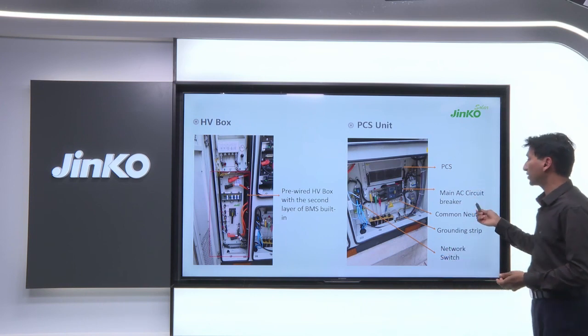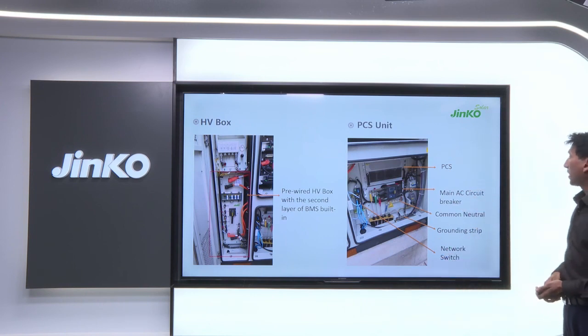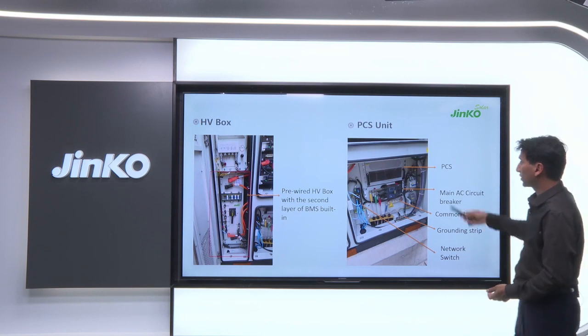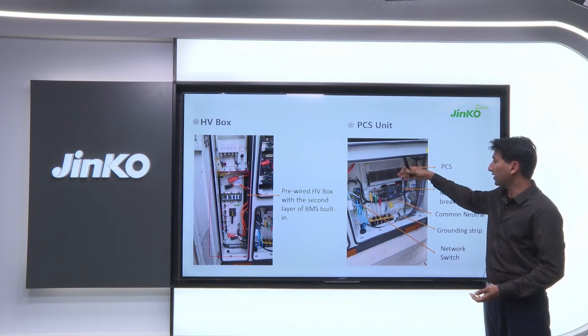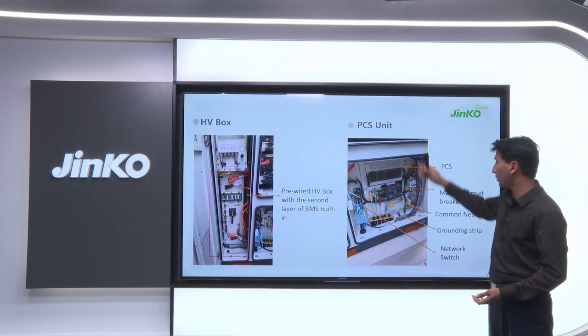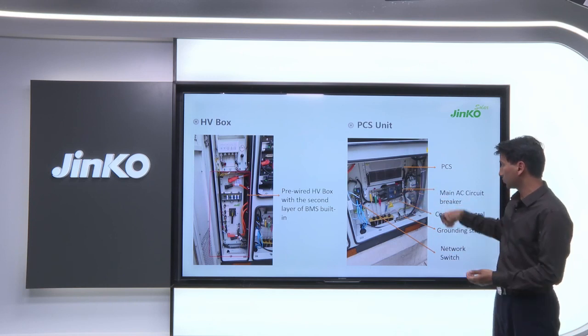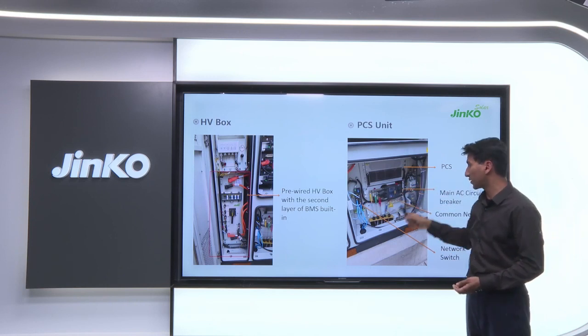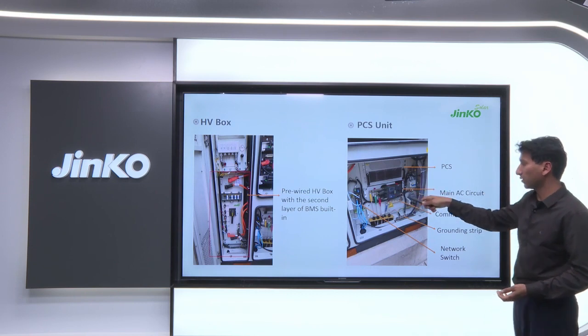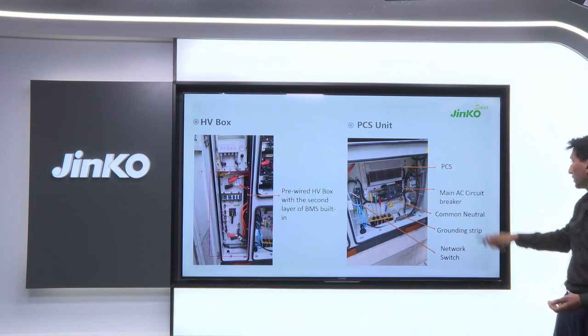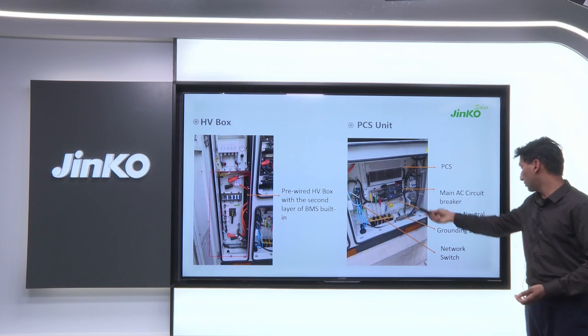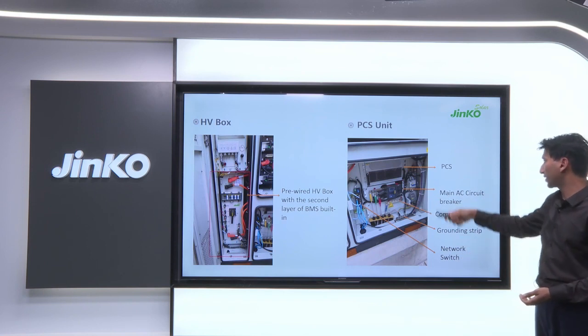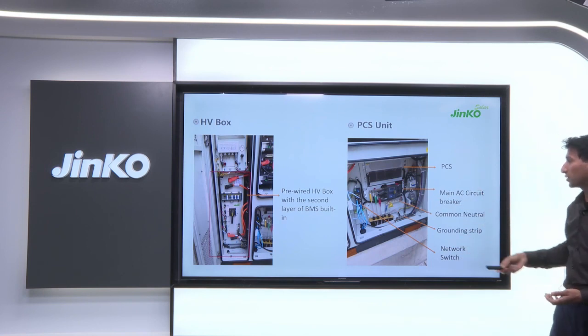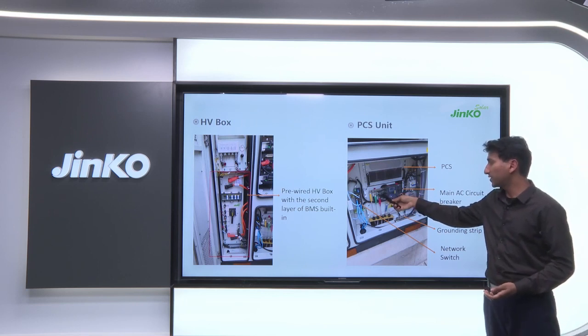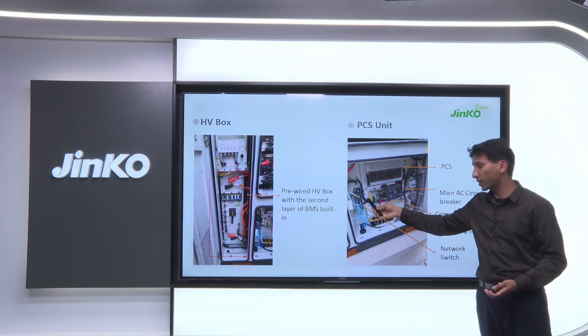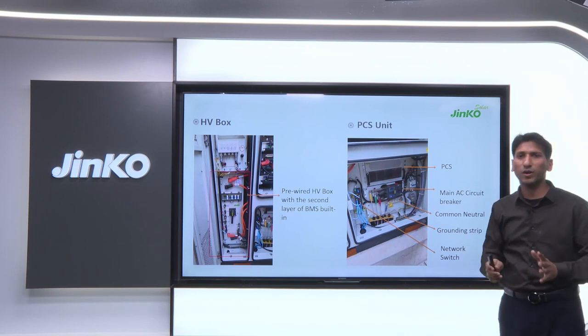Let's move to the PCS unit to know more about this. A PCS unit looks like this. You can see the PCS inside the cabinet, and this is the input-output connector. This is the network switch, which connects all the communication from the slave to the master, along with the common neutral and grounding. They are all connected here, and except for the power cable, the AC connection, and the communication connections, everything is already done. You don't have to do anything on site.